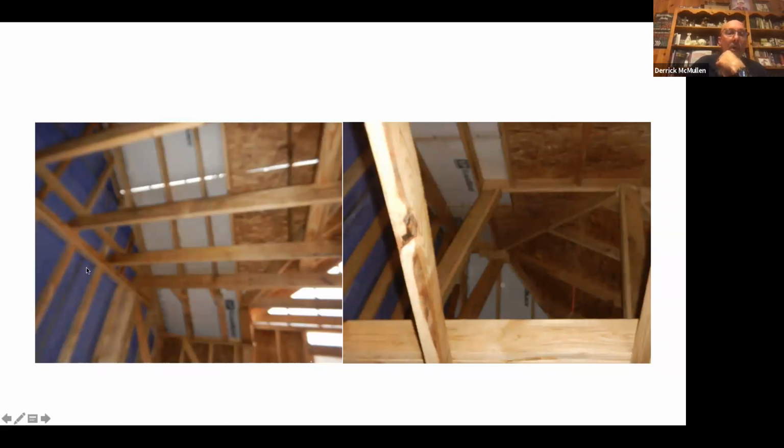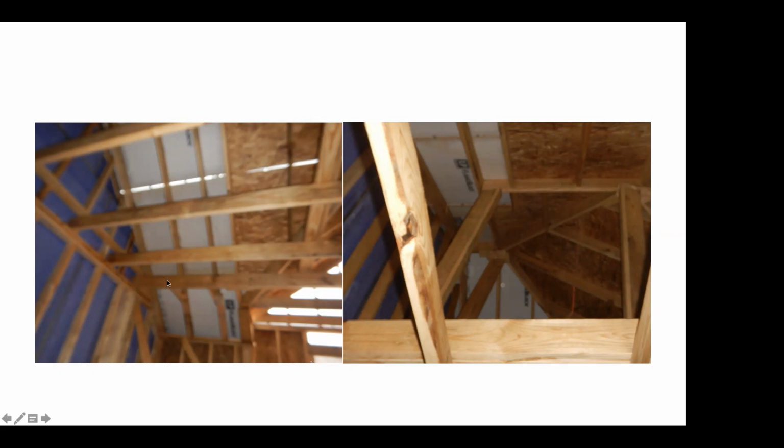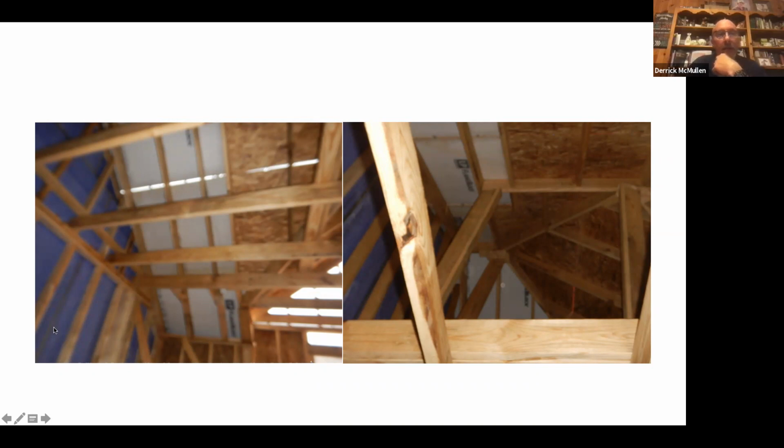On this one, what I see them use is that metal strip, and you can't hardly see it there. Right here, there's a metal strip that they fit into each other. It fits like this on each side. So it creates a barrier there. So this is not required to be taped and floated. There's a channel that goes in there that creates a good tight fit. And this one had three layers of 1 inch Type X gypsum. So I would hate to be the guy that had to move that and install it. That stuff looked heavy. And it was continuous all the way from the foundation. What they did, they ran it up through the roof and then came back and cut it off and then put the roof decking on. But I've not seen this taped and floated.